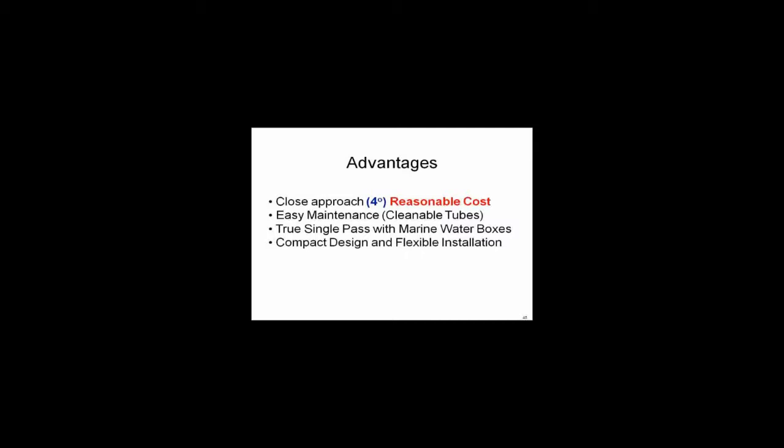So what does series counter flow mean for enhanced tubes, or really, plate heat exchangers? It's the same story. You see the U factor impact by going to enhanced tubes. And what you see on the plot on the left-hand side is a U factor, and what you see across the bottom is just the flow. But look at the U factors themselves. Typical shell and tube, a lower number. By enhancing the tubes, and you saw what enhancement means, you can increase the U factors two or three times. So now, single pass counter flow heat exchangers become practical on a water-side economizer where you want real close approaches. So on a single pass counter flow heat exchanger, four degrees is reasonable. And the reason people are looking at these again is they're cleanable, you can get marine water boxes on them, they're easy to design, and they're very flexible where you put them.